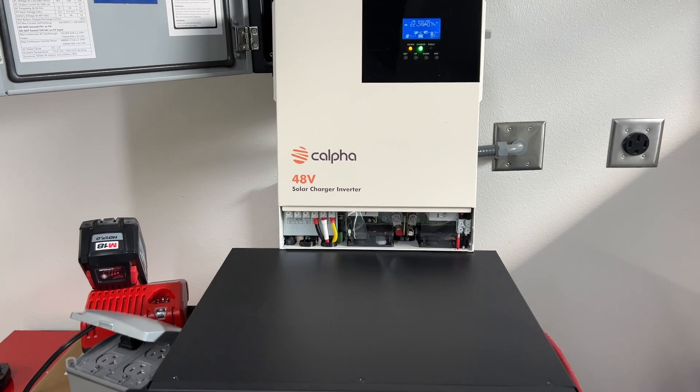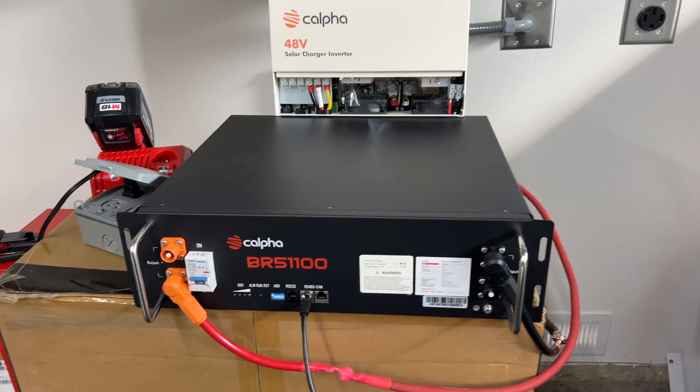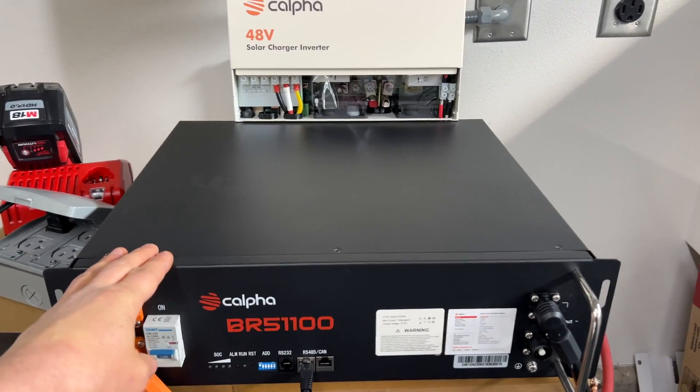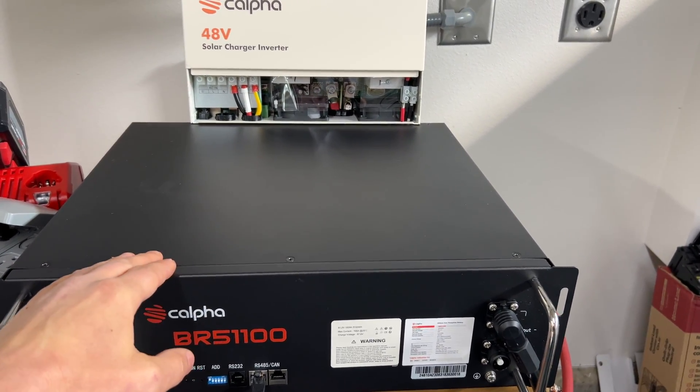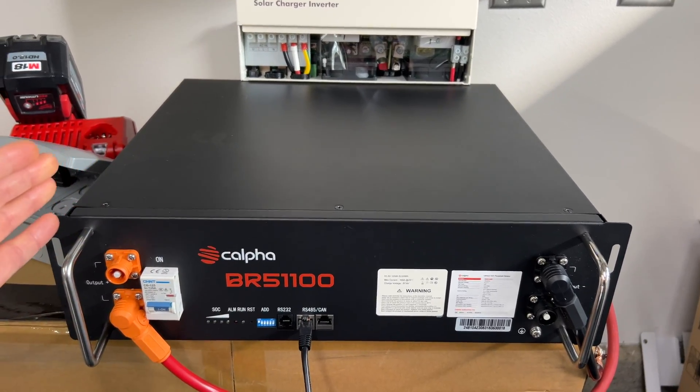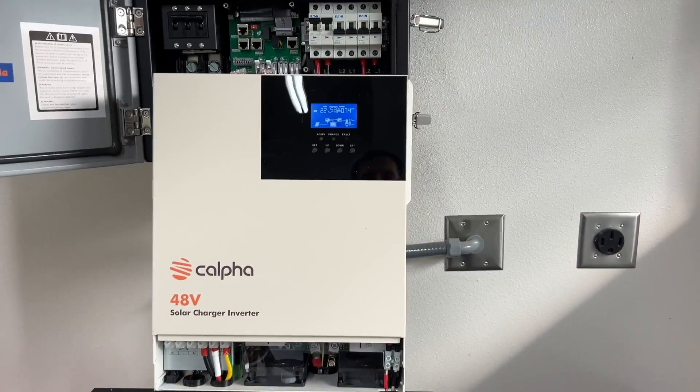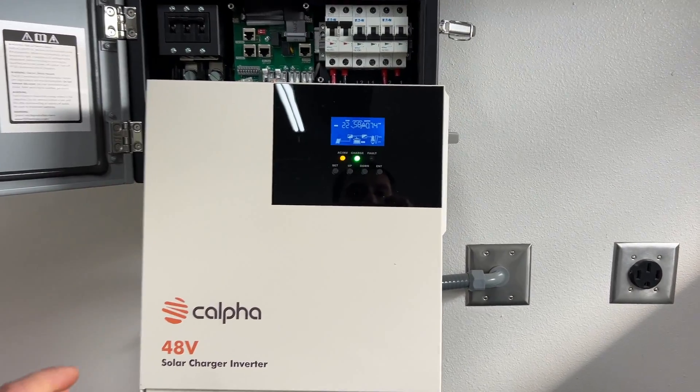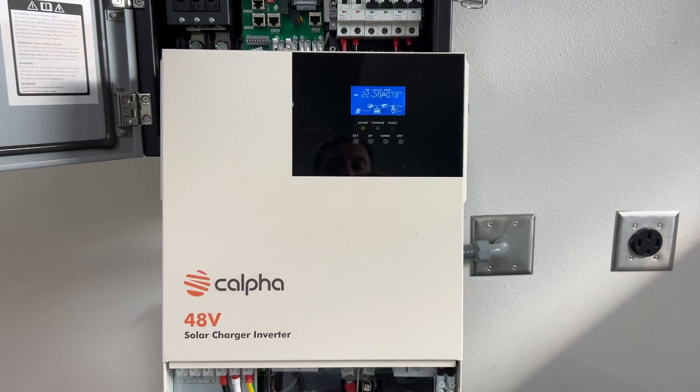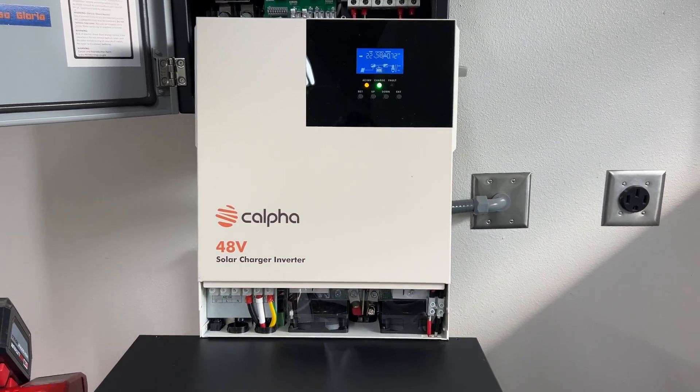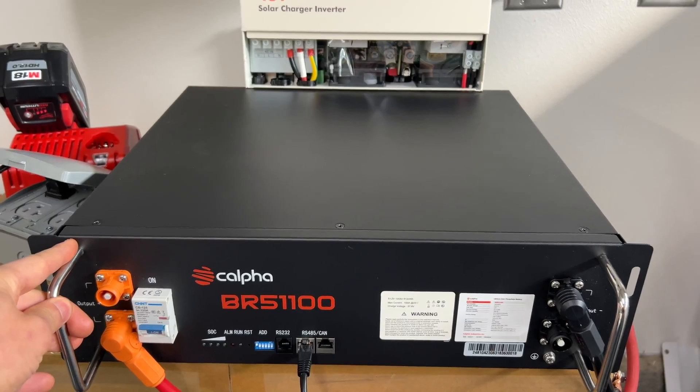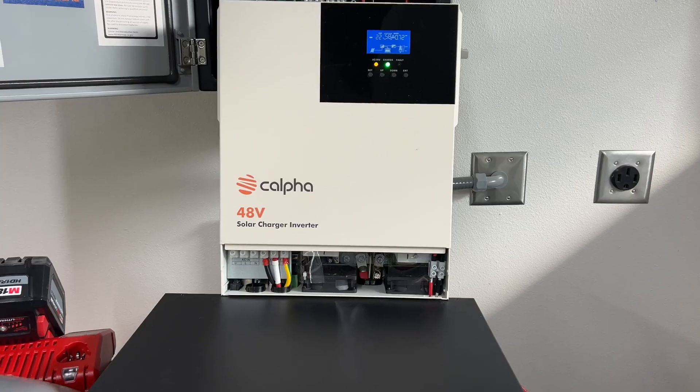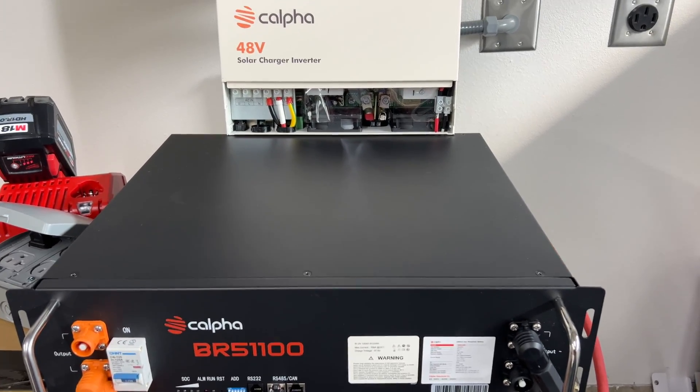That's all tests I want to perform for this unit. Battery showed 98 amp-hours of capacity with 100 amp-hours rated capacity, maybe because it was cold. For inverter, it did perform well with five kilowatts of load test with three space heaters. And same for the battery, it was able to supply 90 amps of continuous load. That's all about this video. Thank you for watching and see you later.